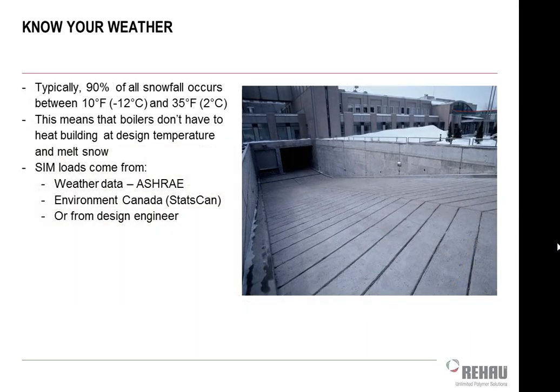Most snowfall, the other thing to think about is, when does it actually occur? It's very rare to get snowfall on the coldest days of the year. So when it's -5, 0, even 10 degrees outside, you're probably not going to have any snowfall. It's just too cold for it to actually snow. Most of the snowfall is going to be occurring probably between 20 and I'd say 35 degrees outside. That's when the bulk of your snow hours are going to be. It's just conducive to making snow.